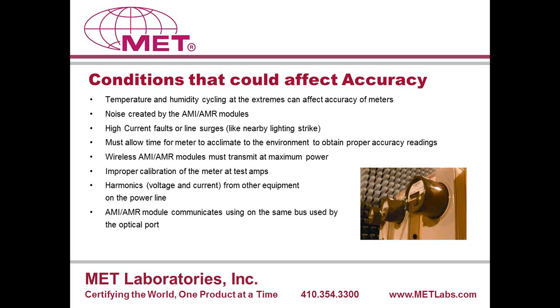Improper calibration of the meter at test amps. The first thing we do before we get into any of the testing at all is run a performance verification, full load, light load, power factor of the meter, just to make sure that it is compliant to the standard and it appears that the meter is properly calibrated. Sometimes right out of the gate, we'll find certain meters do not even meet that criteria, and that happens. But we don't want to get too deep into a test program before we find out that's the case.